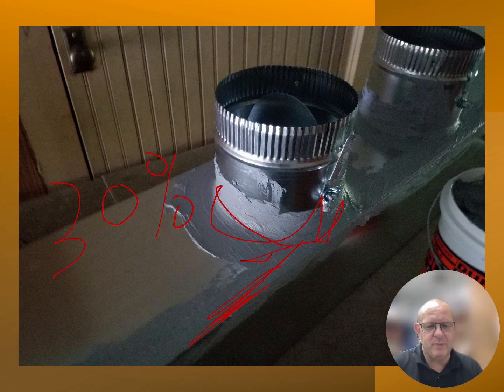And that's why they say that mini splits are so much more efficient than a split system, is because the installers have failed in their installation process of putting mastic or duct seal on the ductwork that's in the attic or in the crawl space or in the conditioned space. We want to seal it. We want to make it nice and tight so that we can have the proper velocity pressure, total pressure, and static pressure within our ductwork. And we don't have to worry about lost conditioned air that we have failed to seal the ductwork up.